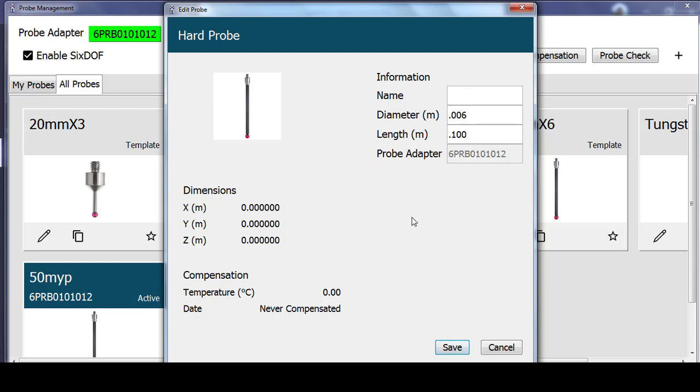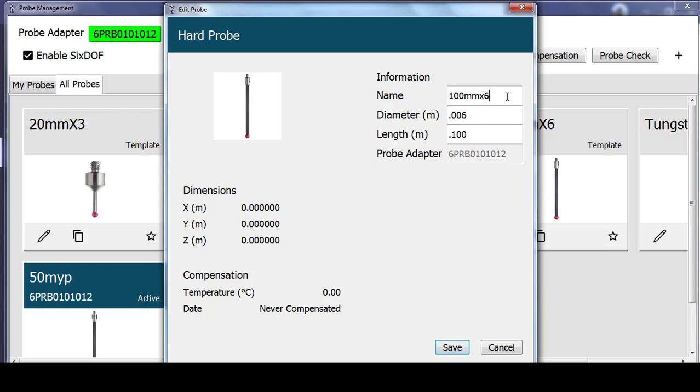And I'm going to name this probe 100x6 so that I know this is the 100mm length and 6mm ball probe. If I want to be consistent with the naming convention that's on these templates, I could change how I label this. So let's do that so that we don't add any confusion. And we'll call this my 100mm x 6 probe. Select save.